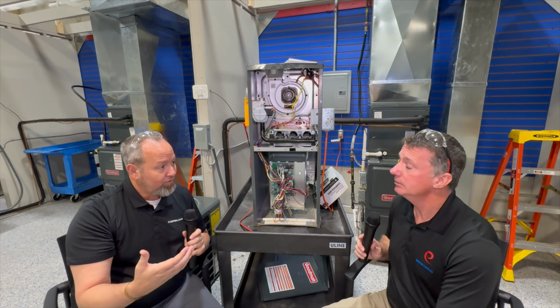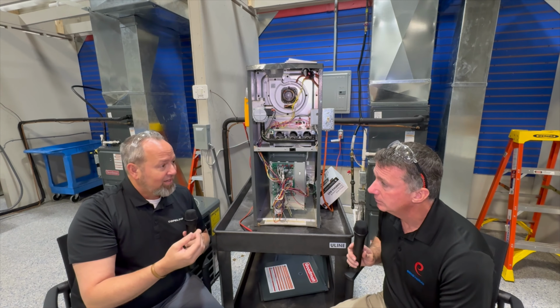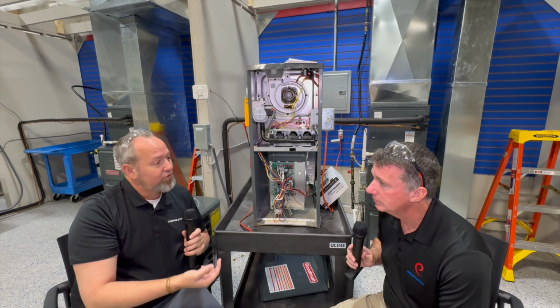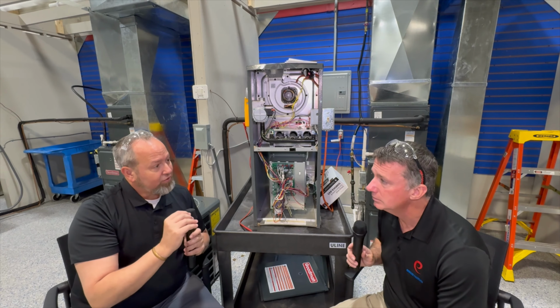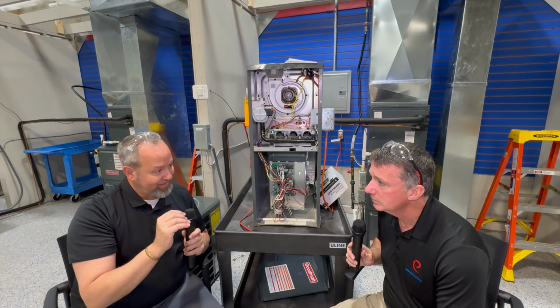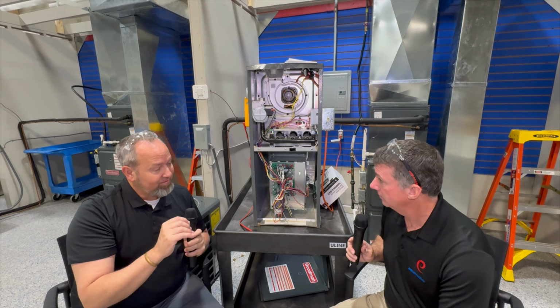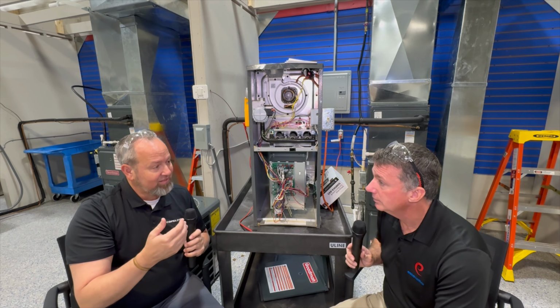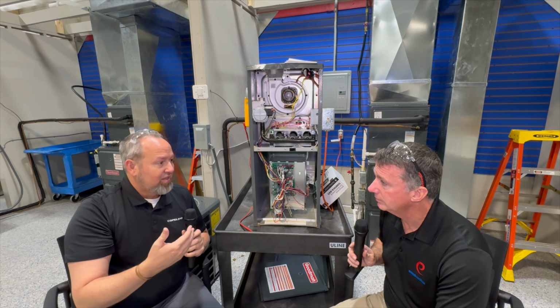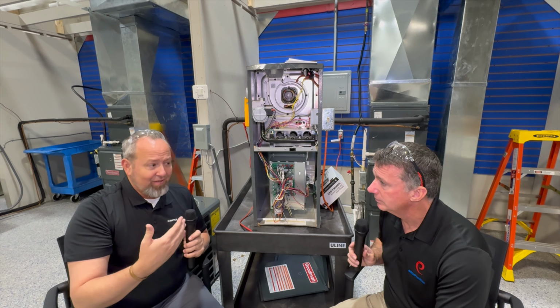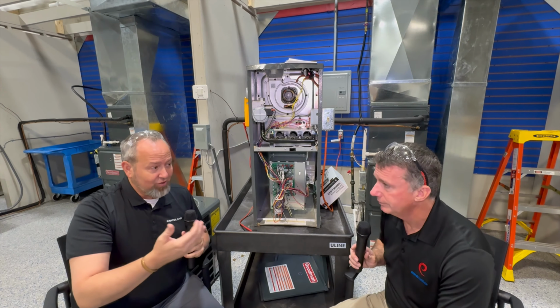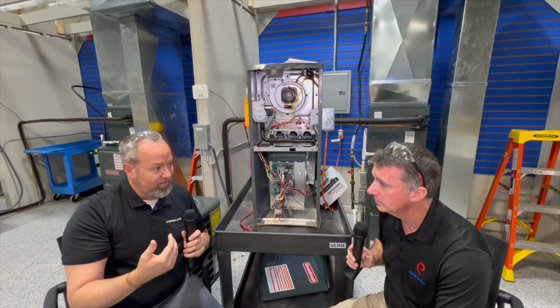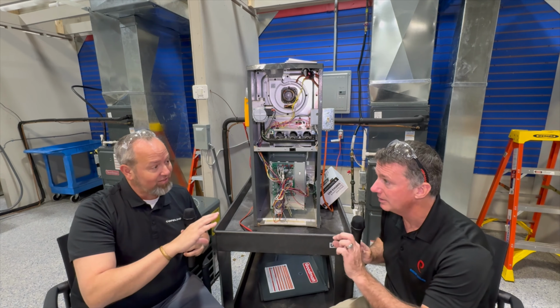So with that, you start testing—you send that 120-volt signal out and it looks for resistance. If it sees at least 75 to 100 ohms on that circuit for our igniter, then it says, okay, this is my igniter circuit.